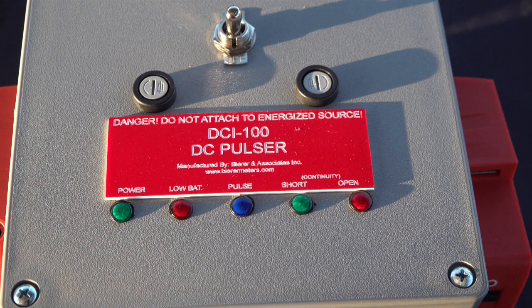The DCI-100 is an industrial battery-powered platform direct current pulsing tool. What makes the DCI-100 unique from other similar type devices is that it is impervious to stray or induced neutral current. In this training video, we will review the DCI-100 itself, the available pulse receiving devices, and the four most common applications the DCI-100 is used for.